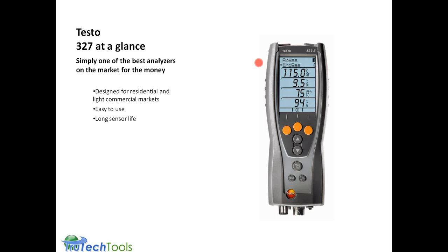It's got a very long sensor life. It's warrantied from the factory for 3 years for both the oxygen and the CO sensor, so you don't have any worries or concerns about the sensors dying on you for a good 36 months or plus. The menus are customizable, so you can get out of it what you want in terms of the order of the display, and we'll get into that in a little bit. There's field serviceable sensors. You can remove the sensors and install your own replacement sensors without the need for calibration.